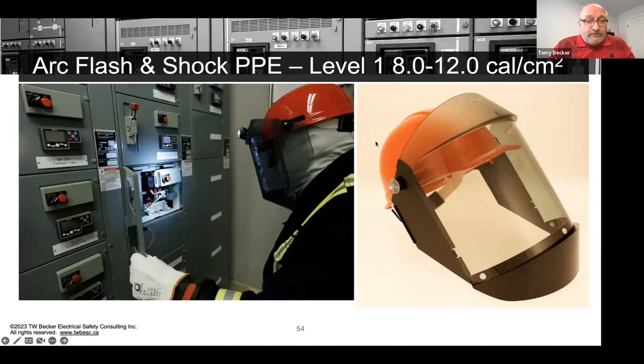So level one arc flash PPE is exactly what I just showed you, sort of graphically. You can see on the left, it's an MCC starter bucket: arc rated face shield, balaclava, ear canal insert earplugs. You need clear approved safety eyewear underneath, because the shield is pretty significant polycarbonate. It's just not rated or tested by the manufacturer to give it the appropriate approvals. And then the arc rated clothing, rubber insulating gloves with leather protectors, provide arc flash protection for the hands, but will not have an ETPV.